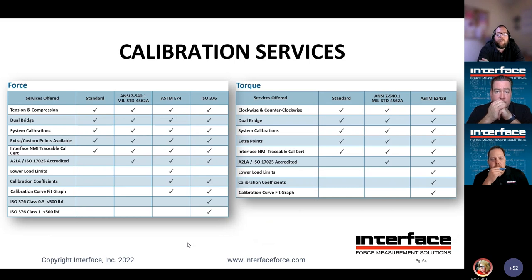So this is a variety of the calibration services that we offer. We can do standard ISO 17025 A2LA accredited calibrations, ASTM E74 and ISO 376 on force. And from the torque side, we can do the A2LA Z540, as well as the ASTM E2428. And those do come with calibration certificates that provide additional information depending on the calibration that's provided. Next slide.